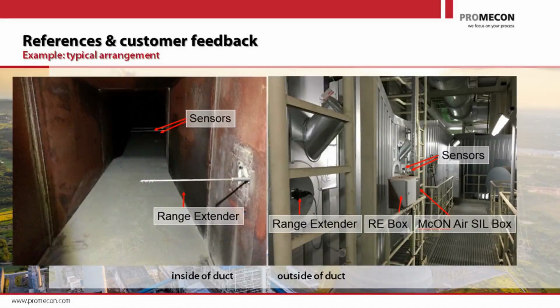I've shown you a picture of a trend that is drifting from the Alstom boiler. I guess you remember this picture of the 800 megawatt Alstom boiler. This is a boiler in Germany. And you can see here the original venturi. It's not a real venturi, but it's similar. And that has been failing. You can see on the right-hand picture from the outside, the installation, and on the left-hand picture from the inside.